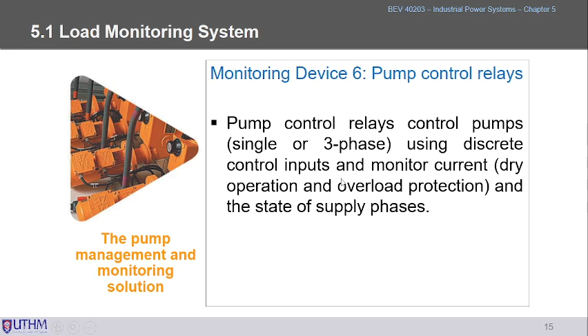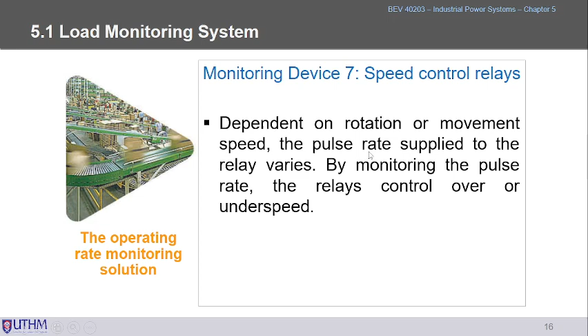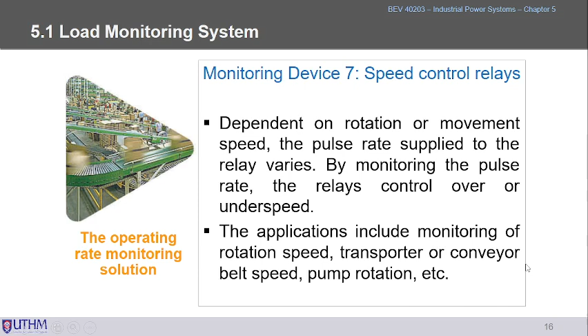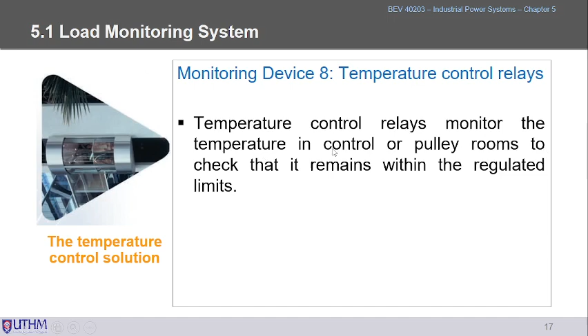For operating rates monitoring solutions, for example when we want to know the operation of our motors or machines, we can use speed control relays to maintain certain motor speeds. So we know whether there are under-speed or over-speed problems, in the MCC especially. For temperature control solutions, temperature control relays can be used to control and monitor the temperature, especially in the pulley rooms, to check whether it remains within the regulated limit or not.